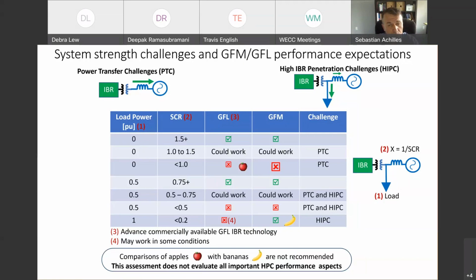If we have local load, it is possible for several grid following concepts to work stably with short circuit ratios below 1, like for example, 0.75. And grid forming is also expected to work. As we reduce the short circuit ratio, we see a similar behavior as what we saw before with the load 0. There is an area where the power transfer is challenged, where both of them could work or may not work. And then if we go below what you can transfer through the system, it will just not work for either of them, grid forming or grid following.